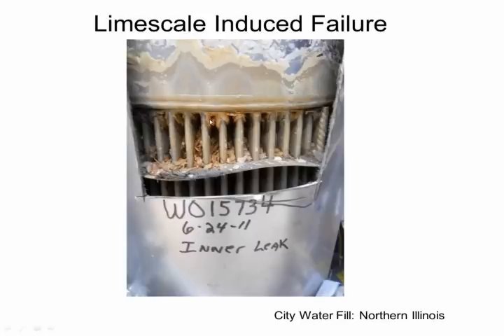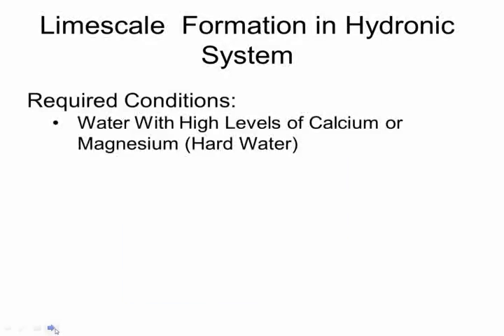But limescale likes to build up where the temperature is hottest, and the temperature is hottest in this particular boiler at the top before the water leaves the system to go back out to the system, okay? So you have insulation capabilities up there, so the metal is actually hotter up here, relatively cooler down there. Different temperatures on the same piece of metal cause thermal stresses, and that time-temperature effect causes what? Basically failure and leakage in this case. So, okay, what causes limescale to begin with?